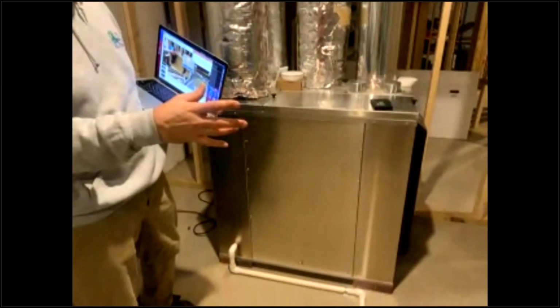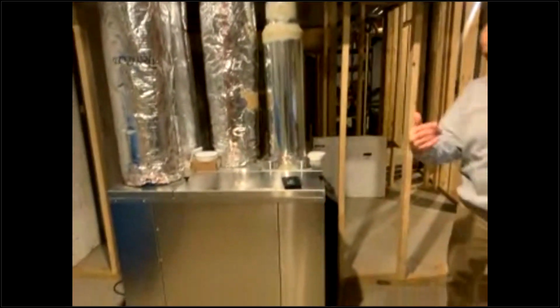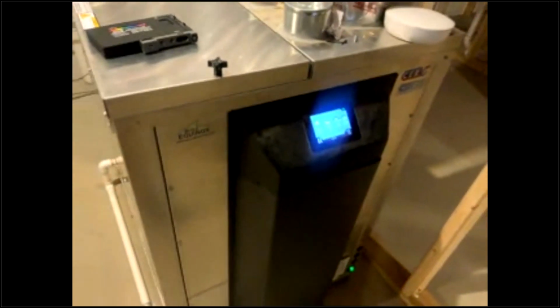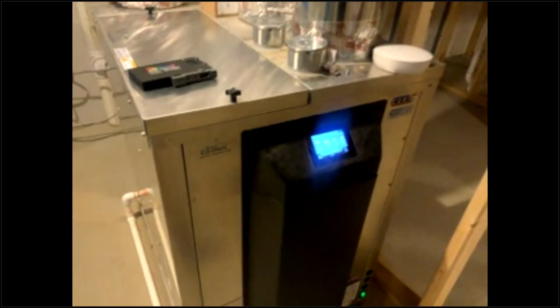And this is the ERV, the conditioning ERV, which you did mention some details about before. It is that brand of the sponsor. So I can show you over here. That's a real-time view of the conditions right now with the sensors. It's a little bit hard to see. Maybe back up a little bit. Okay. So it's giving you the conditions of temperature, humidity, CO2, and VOCs. And we're doing our set point control off of CO2 level.